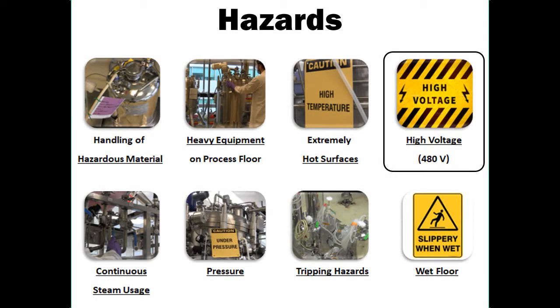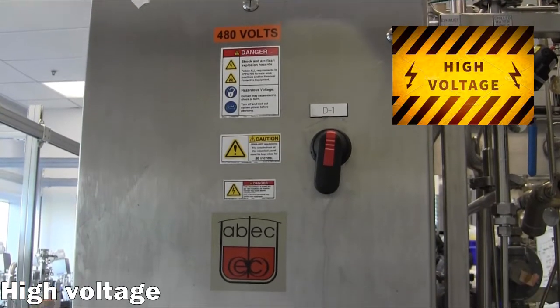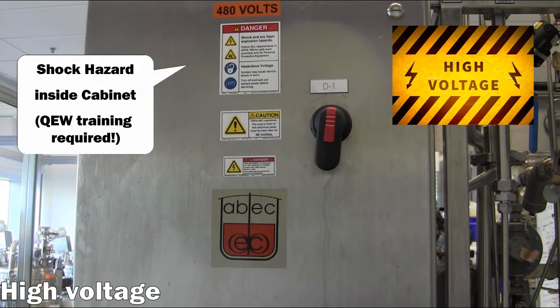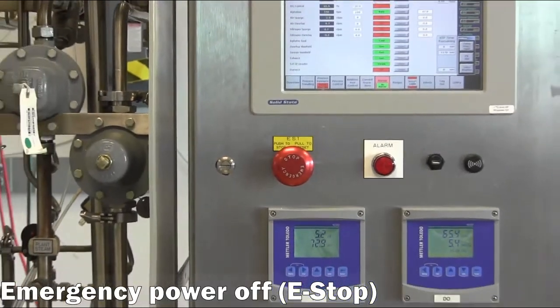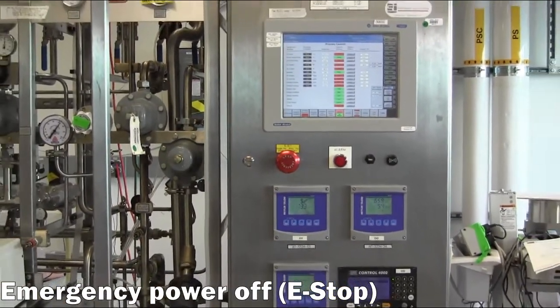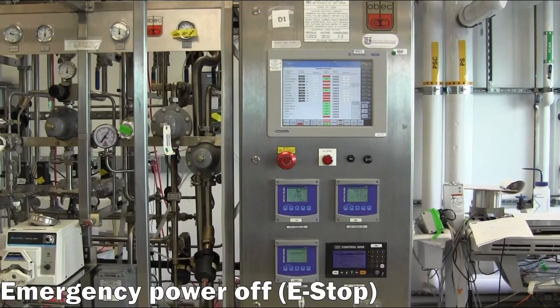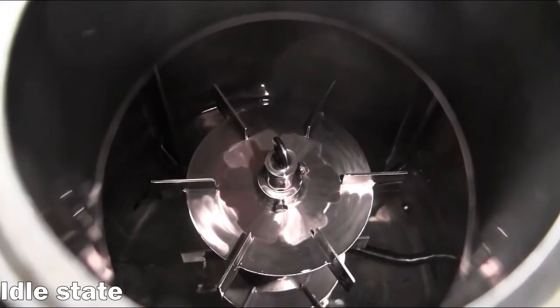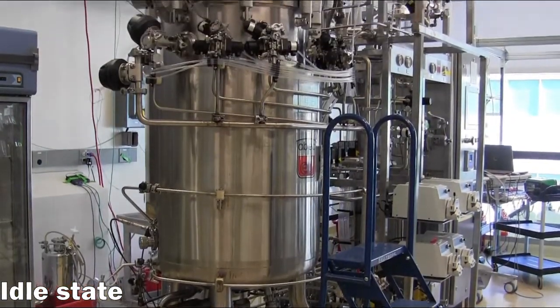Given the scale of the reactor, the energy requirements are also significant. Shock or arc flash from a 480-volt source can cause serious injury or death. For general operation, it is critical that lab operators have completed the requisite electrical switching training and wear appropriate personal protective equipment while powering up the reactor skid. The 480-volt cabinet powering the skid creates a shock hazard when opened. As such, only qualified electrical workers are able to work inside for any reason. In case of an emergency, there is an emergency power off, or E-stop, on the main control panel of the reactors. The E-stop will shut valves, turn off the agitator, and put the reactor in an idle state until the emergency status is lifted.